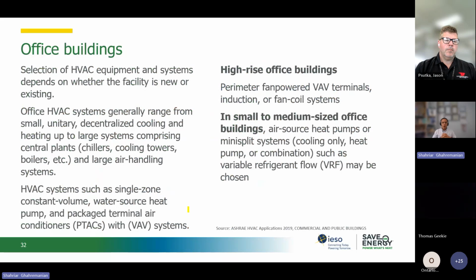Now let's look at what ASHRAE and other standards mention about building systems. So let's look at the office building. It depends on the size of the building. It's a high-rise office building or a small to medium-sized office building. So again, depending on the system, we can go with perimeter fan-powered VAV terminals, or induction or fan coil systems, or for a small to medium-sized office, we can consider heat pumps, either mini splits or the VRF as well. Or if the size allows, then we can go with a packaged terminal air conditioner, a VAV system, or a single-zone constant volume system, for example, water source heat pumps as well. So any of these systems can be considered for an office building.